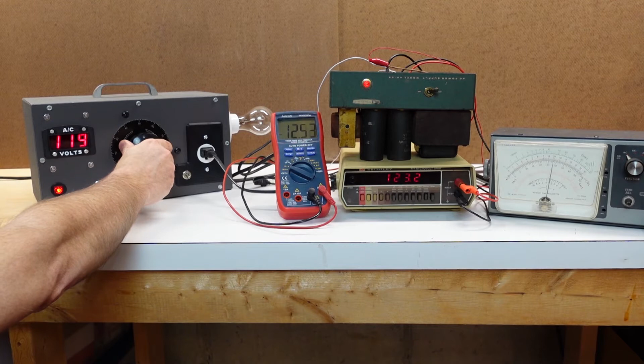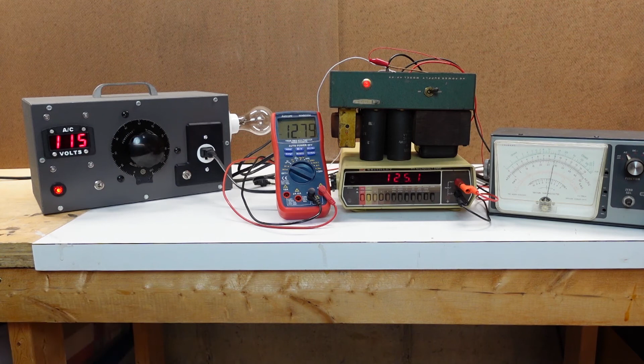I'll stop here around 115, that ought to be good enough. Looking at the readings, 12.8, that looks good. 125, that looks good. And that needle on the vacuum tube voltmeter is around 280-ish, give or take. So that also looks good. And the indicator is glowing on the power supply. This is good. It looks like I've got a good transformer here, and I can proceed with rebuilding this power supply.